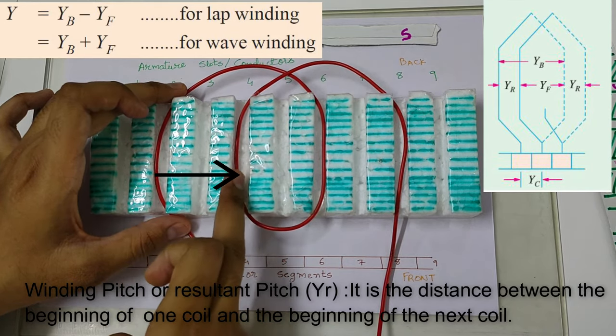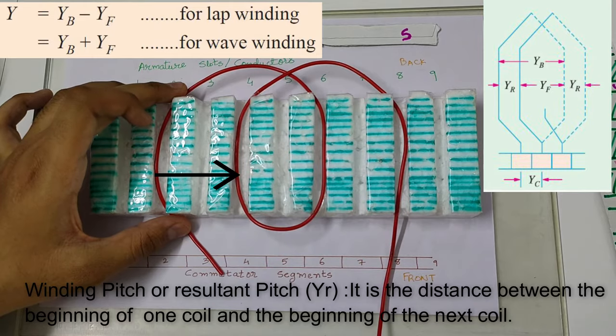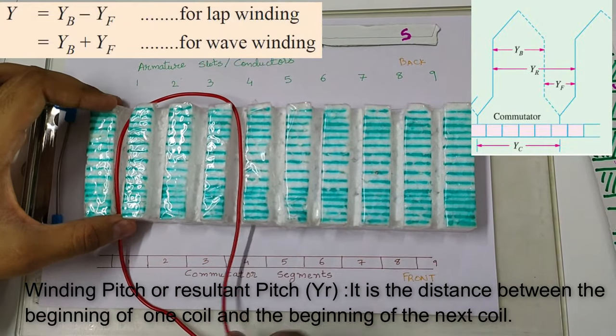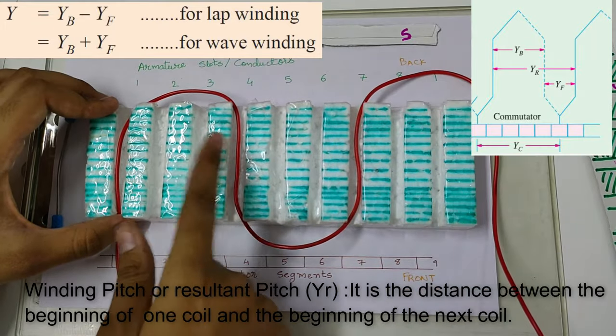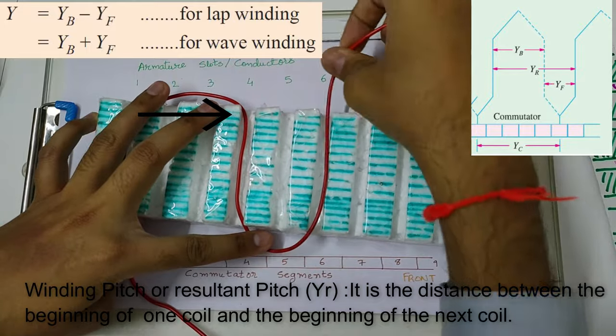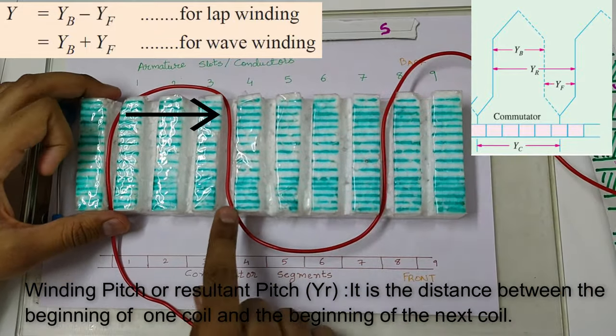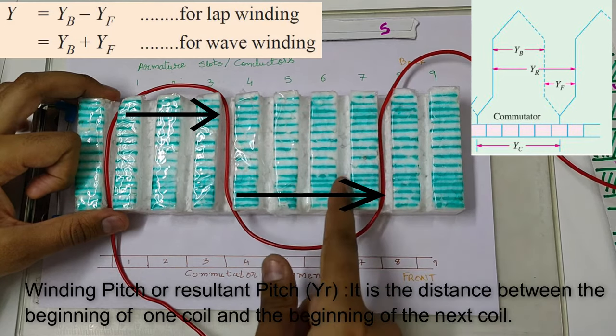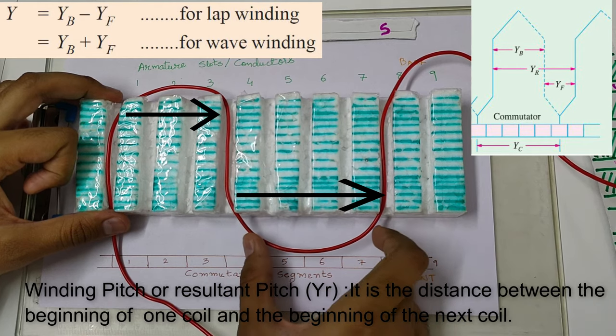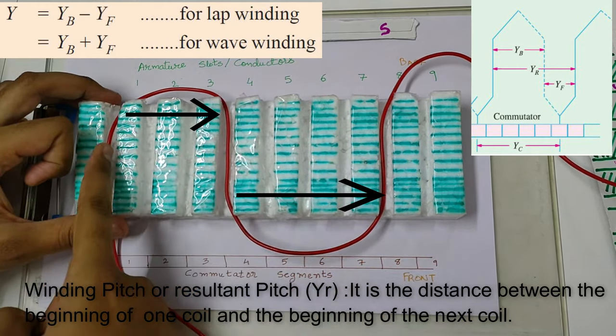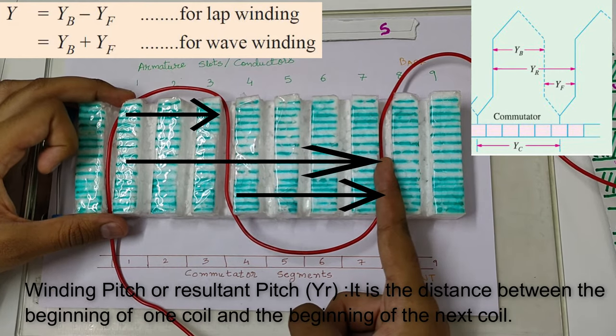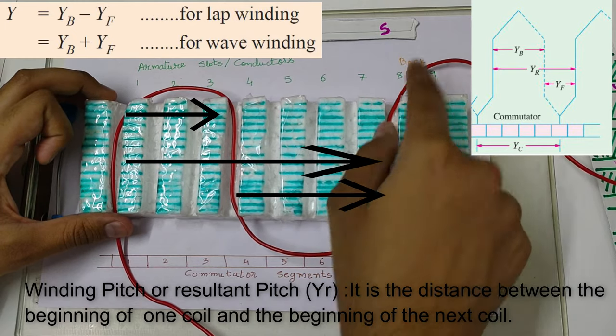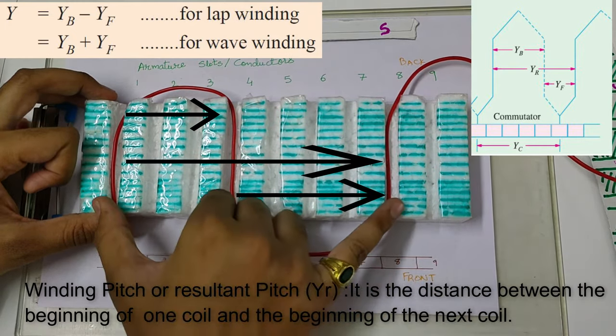We can also have a resultant pitch of 2 if the winding starts at a distance of 2 slots from the first winding. Now in case of a wave winding, the back pitch — for example, starting from 1 and going to 4 — so 1, 2 and 3. So 3 is the back pitch. For the front pitch, the distance between the end of the first turn and the start of the second coil is 1, 2, 3 and 4. So front pitch is 4 and back pitch is 3. The resultant pitch — distance between the starting of the first coil and starting of the second coil — is 1, 2, 3, 4, 5, 6 and 7. So the resultant pitch is 7 in case of a wave winding, or we can calculate it as 8 minus 1.